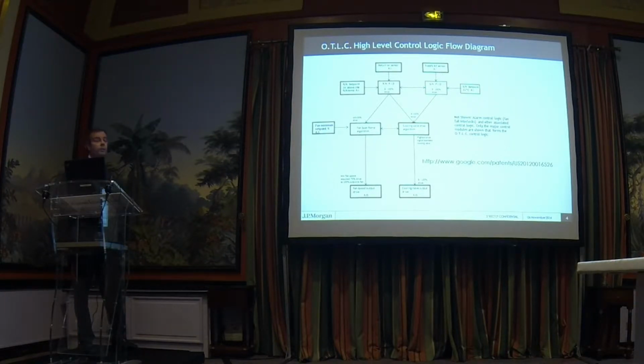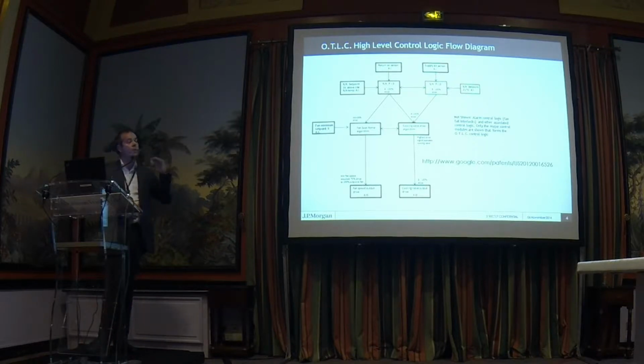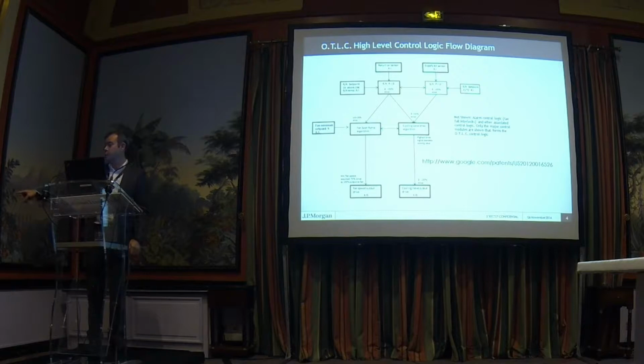So now that we set this here to 21 degrees supply, the return air set point, mind you, is then set a degree above whatever that CRAC unit is doing. So if it's got 28, that one's got 30, this one's got 22, I just set it for 1 degree above its actual running temperature, because the data center is pretty static in the way the temperatures return back to CRAC units. The moment that the return air begins to elevate, this is where the system kicks in, and it will then override the 21 degree set point and start driving the 21 degrees, 20, 19, 18.